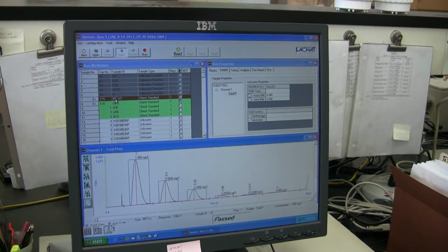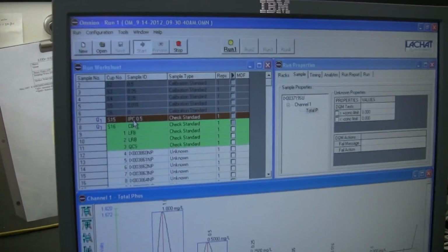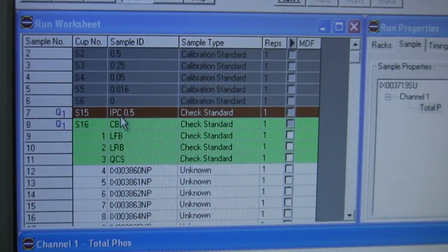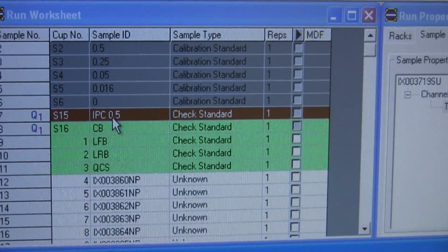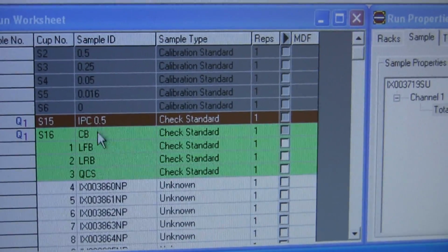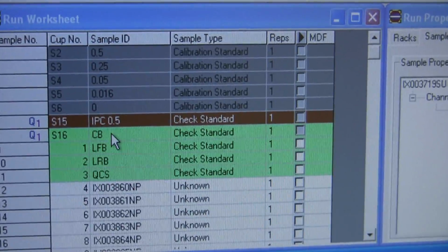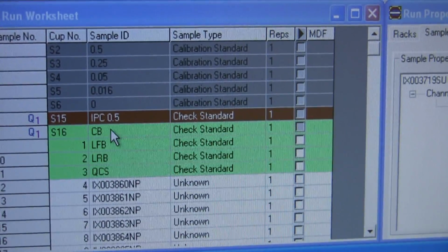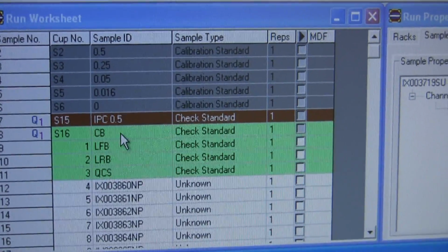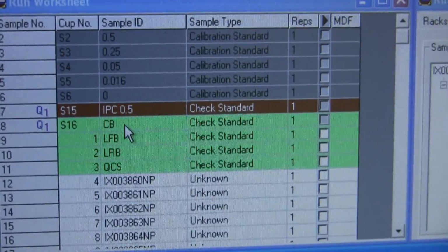So right now, IPC stands for Instrument Performance Check, and a check blank is what it's running next. It'll run these two standards every 10 samples, and that's just to show that the instrument does not drift out of calibration, by checking a midpoint standard and a zero.